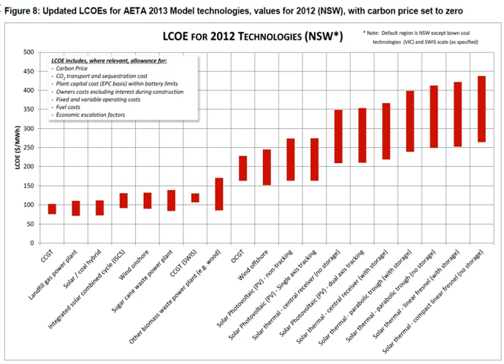Fuel costs are high for fossil fuel and biomass sources, low for nuclear, and zero for many renewables. Fuel costs can vary somewhat unpredictably over the life of the generating equipment due to political and other factors. Works power, or parasitic load — the portion of generated power actually used to run the station's pumps and fans — has to be allowed for. To evaluate the total cost of production of electricity, the streams of costs are converted to a net present value using the time value of money, brought together using discounted cash flow.